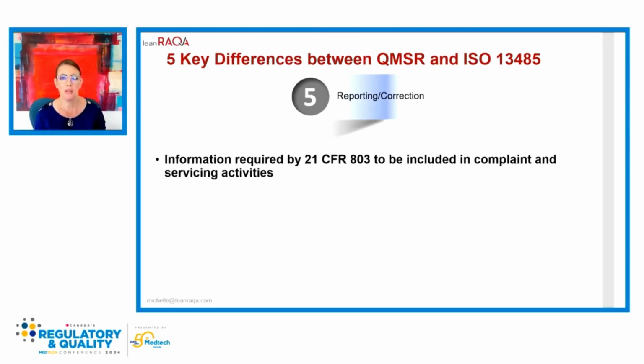definition change that the FDA said is, not only are we recognizing the term correction in terms of field corrections that you may take on product that's left your distribution, but we're also recognizing that the term correction could fall within your corrective and preventive action procedure as an internal correction to product that you might have reworked underneath a material review board or nonconformance inside your control.